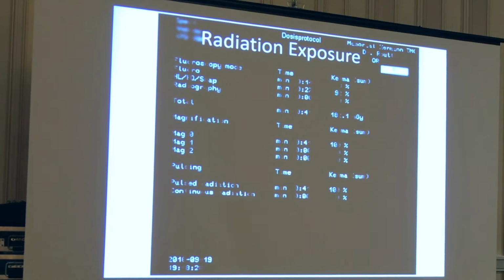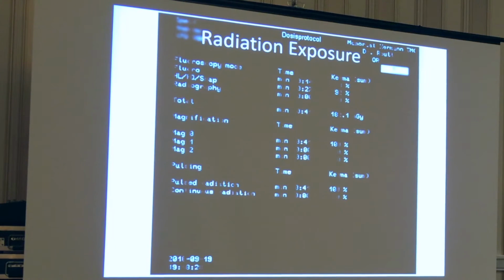182 milligrays. And so you can also see that, Johnny, are you still here? Yes, back here. Can you just tell them like how many images it gets per second and stuff like that? It acquires 400 images and then reconstructs those images in about 45 to 50 seconds. So it's 10 images per second. It takes about 40 seconds. And how long does it process them? It takes 45 seconds to do the spin. And now keep in mind, that equates to only 9 seconds of fluoro time. And the reason for that is because the generator is in the pulse fluoro mode. So it equates to only 9 seconds of fluoro time.